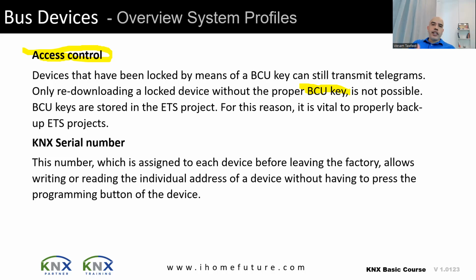By the way, if you forget the BCU key, the only way to recover the device and get it back to factory default is to send it to the manufacturer itself. There is no workaround that you can do as an integrator. The manufacturer will reset it to factory default and send it back to you. Okay, but the operation will be normal even if you don't know the BCU key. You only need it if you want to make changes to the installation that you did.